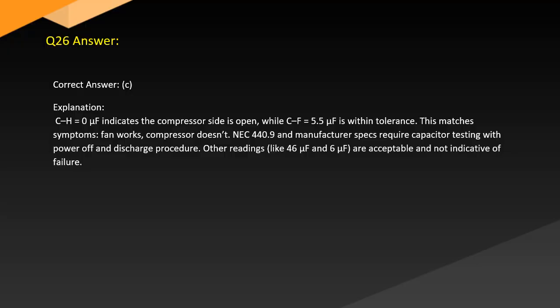Answer. Correct answer. C. Explanation. CH equals 0 µF indicates the compressor side is open, while CF equals 5.5 µF is within tolerance. This matches the symptoms: the fan works, the compressor doesn't. NEC 440.9 and manufacturer specs require capacitor testing with power off and a discharge procedure. Other readings like 46 µF and 6 µF are acceptable and not indicative of failure.